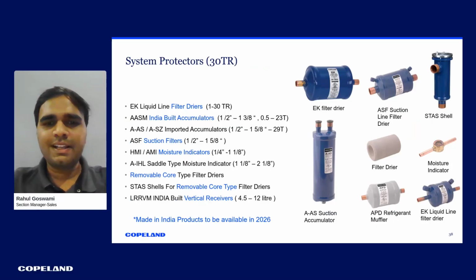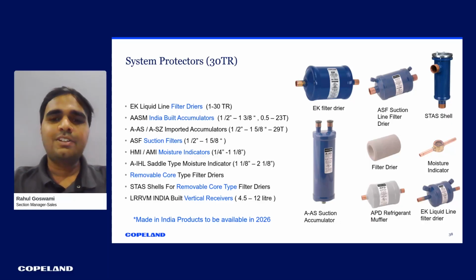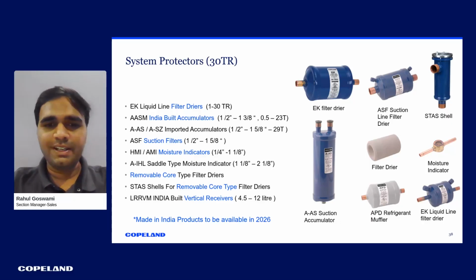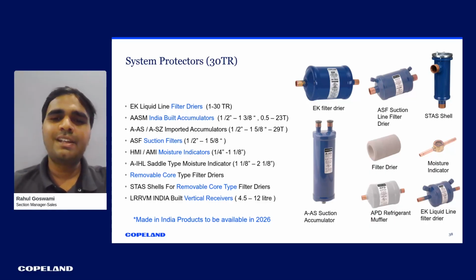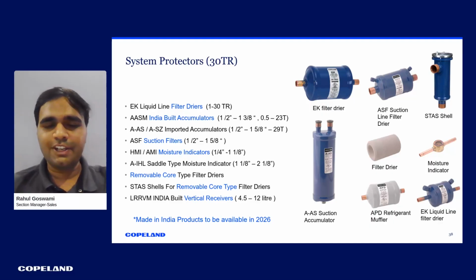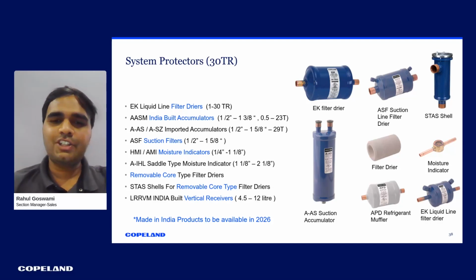So next products are basically these system protectors. These are used to protect your systems from various debris, dirt, moisture, if there is any in the refrigerant. So first product is filter dryer. Filter dryer we have up till the solution of 30 TR. We have accumulators, which are now an Indian make. So we have Indian make accumulator up to 23 TR. We have accumulators which are manufactured by Copeland globally, which are AAS and ASZ series. We have suction filters. Then we have moisture level indicator, which is basically used to see the state of the refrigerant, whether it is in gaseous state or liquid state.